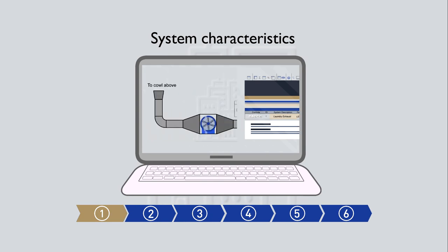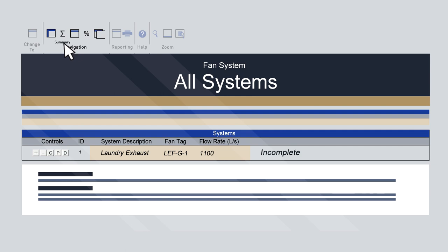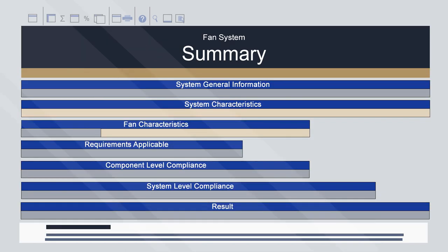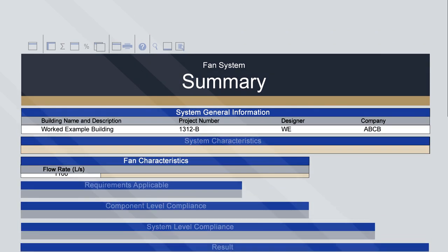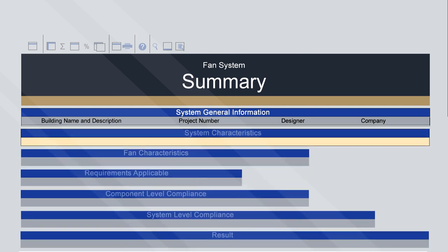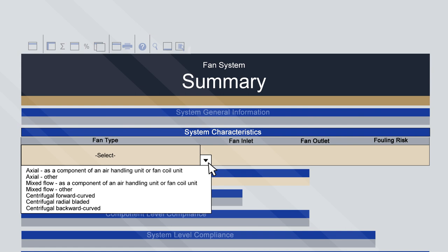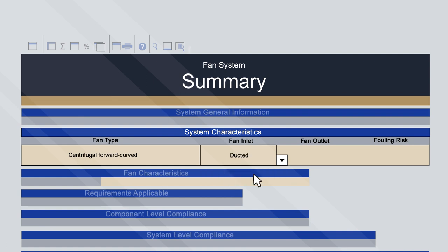Step 2: system characteristics. Navigate to the Summary sheet using the ribbon. This sheet serves as a hub for system-wide information and results. You'll notice that the project information and flow rate is prefilled from the previous step. Select the system characteristics using the drop-down menus. For this example, we'll select a centrifugal forward curved fan, with a ducted inlet, a ducted outlet and lint representing a fouling risk.